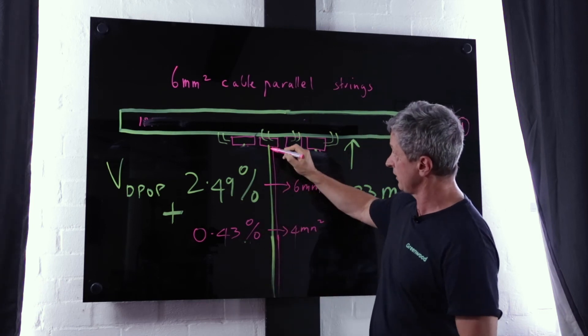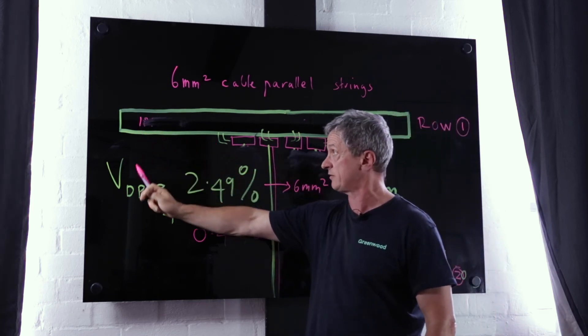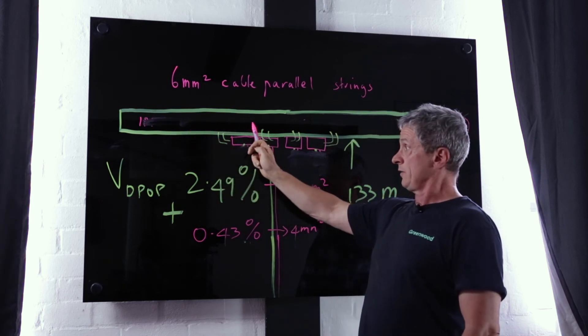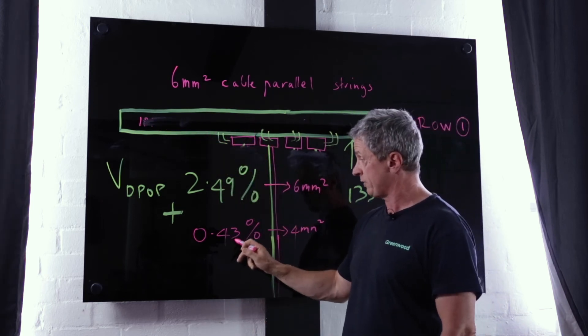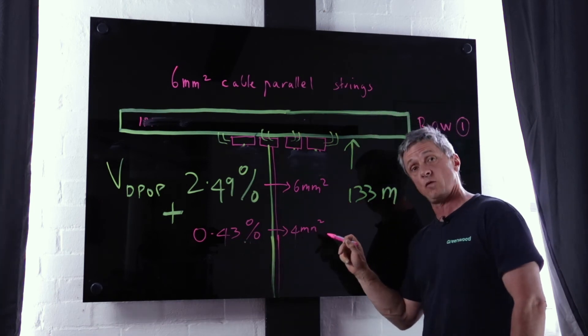Now that's getting a little bit close to that 3% so it probably is advantageous on this row to use 6mm all the way through to bring that overall volt drop calculation down the percentage.